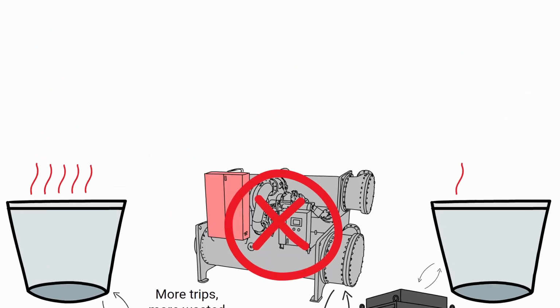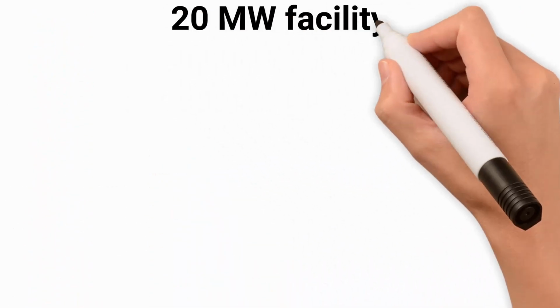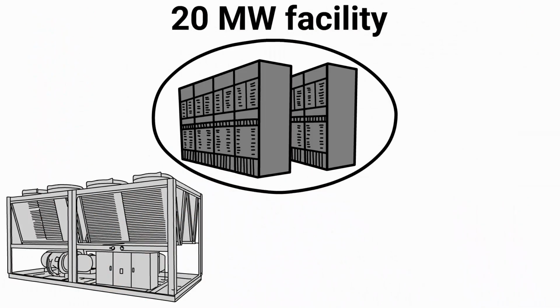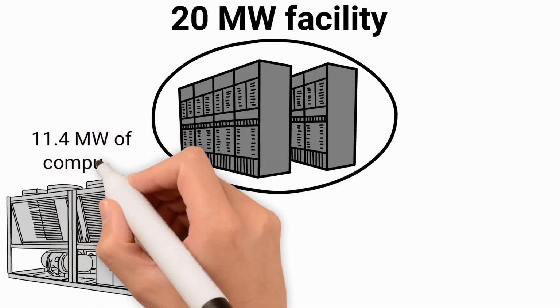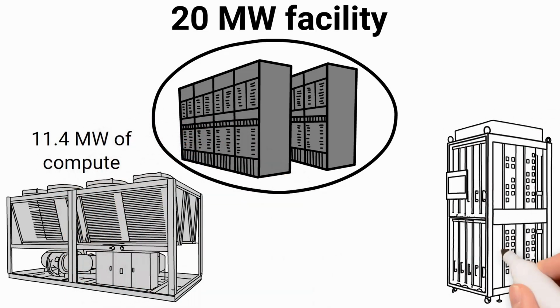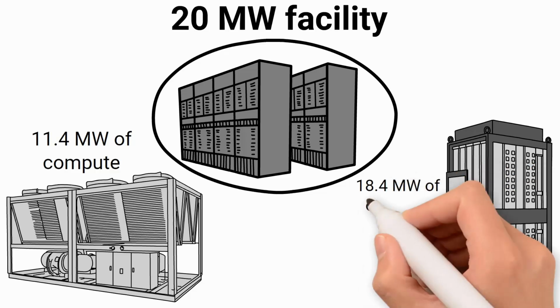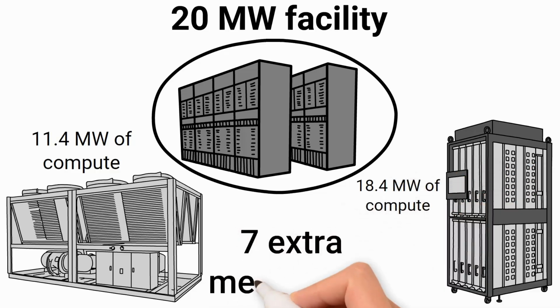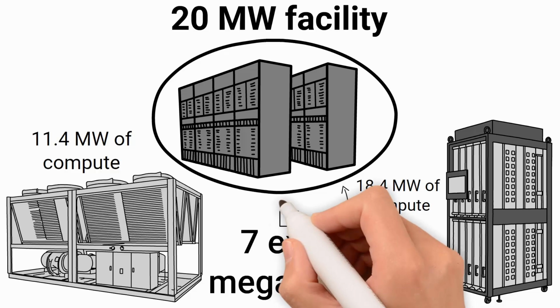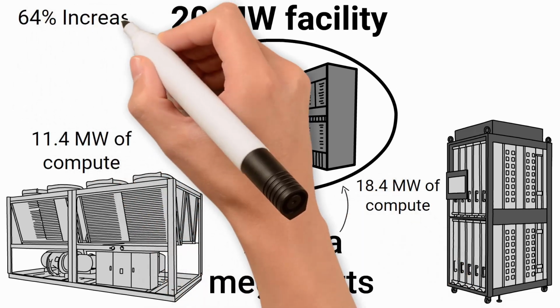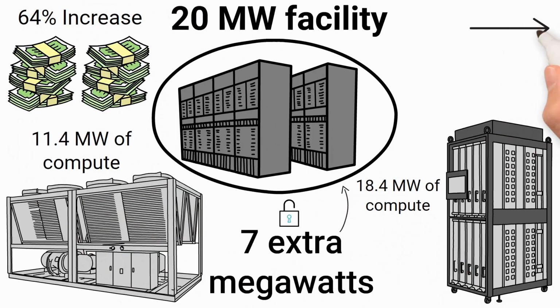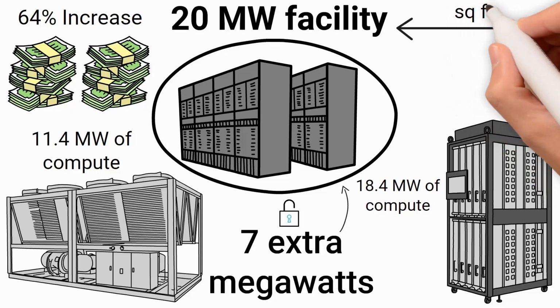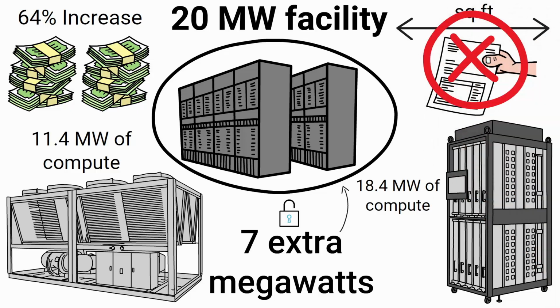The impact is dramatic. At a 20 megawatt facility, air cooling delivers about 11.4 megawatts of compute. With liquid rack, that number jumps to 18.4 megawatts. That's 7 extra megawatts of compute capacity unlocked, a 64% increase in revenue density without adding a single square foot of space or negotiating new power contracts.